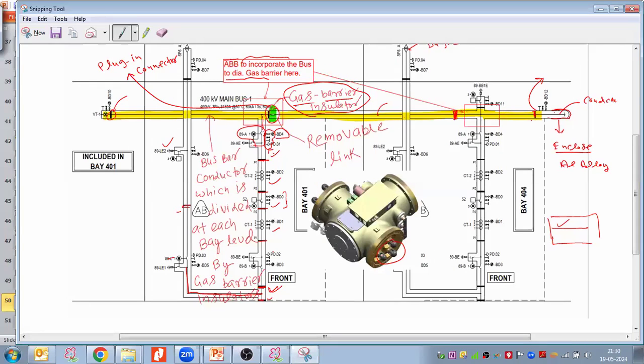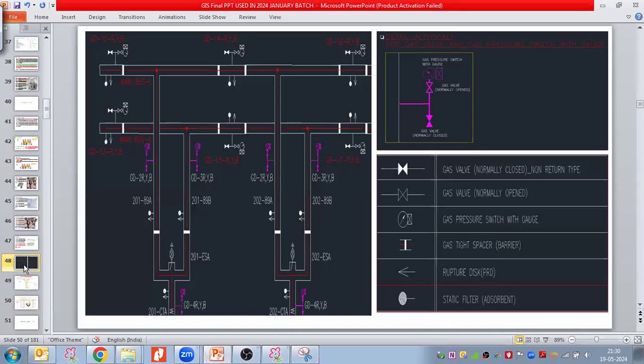Plug-in connectors. Could you see this one? Here, these are our bus bar modules, and the connector goes through the modules. If this is 3-phase, then R Y B is coming, but this is plug-in connectors. I'll take this point as well. These are as per male-female contacts, a plug-in connector for the conductors, so that it can easily connect from one bay to another. To connect the two bays, we use this type of connector for the conductor connection.